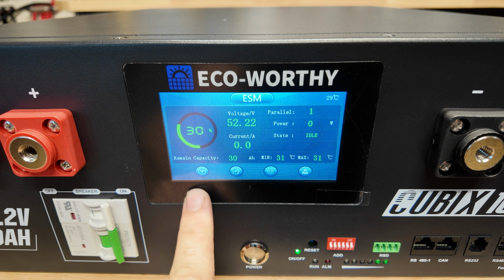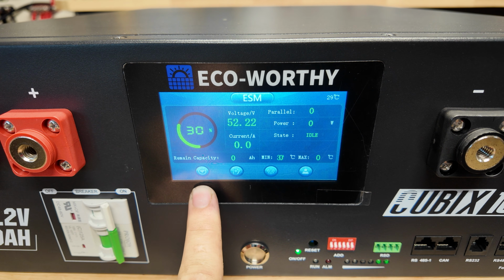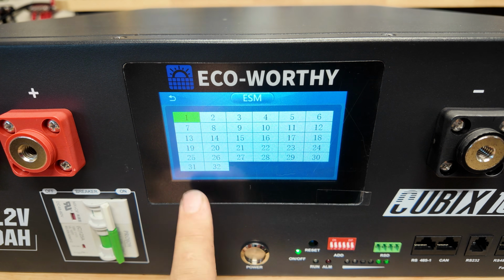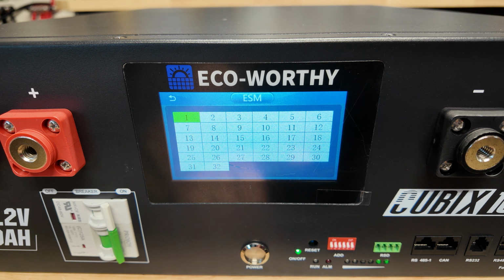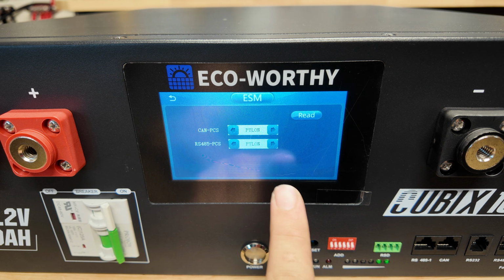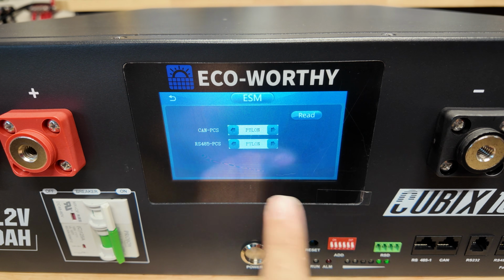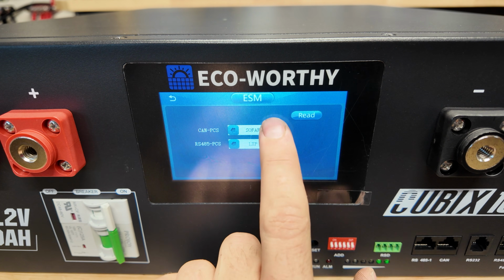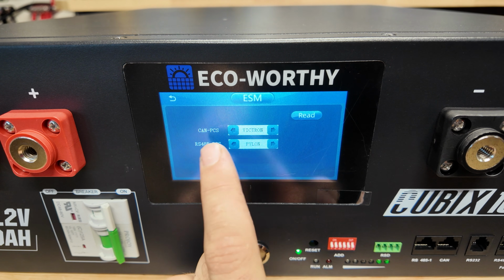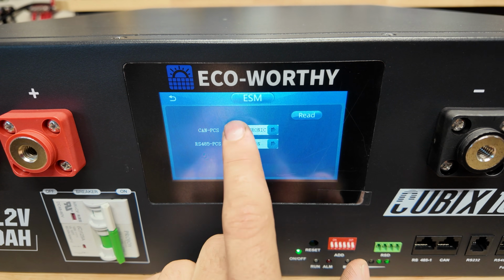We also have a couple options down here. This button right here lets you see the other statuses of your other batteries. If we click here, it shows we only have one because we don't have any in parallel. Here's where we're going to set our communication protocol. It comes out of the box set to pylon. You can use these arrows right here to go through the different menus and pick whatever one is compatible with your system or your inverter.